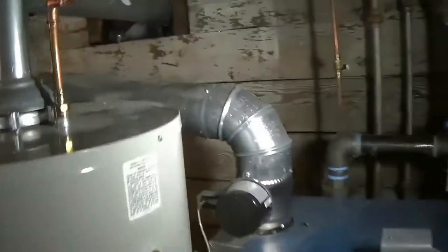So now we're identifying the systems. So I've already asked these guys, they're getting pretty good at identifying stuff. So it is a boiler. It is fired by gas. So the ways that you figure that out, this is your gas line, this nice black pipe. There's a gas valve down there. You don't have a big oil burner hanging off the front. So it's a gas-fired, atmospherically vented. We've got a chimney here that these metal flue connectors hook up to, so that means atmospheric.